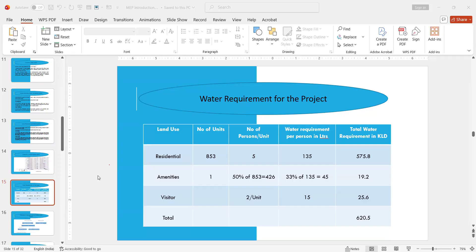So if a project has 853 flats of 2.5 or 3 BHK, the water requirement will be 620.5, and our tank should be around this much. According to this calculation, the capacity of the tank for your particular project will be designed. When you see it, it will come around this much, plus minus 10 or 20% safety factor that designers take, but it will be a lump sum like this only.